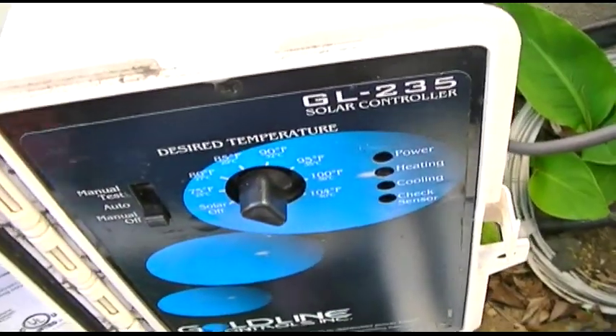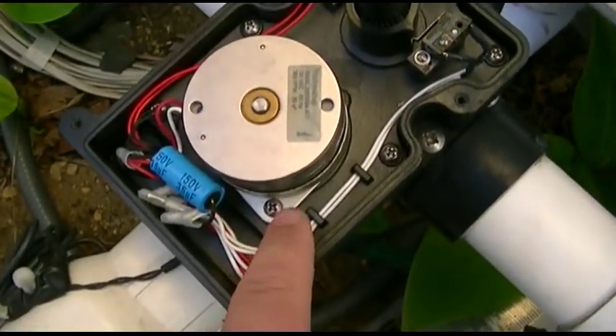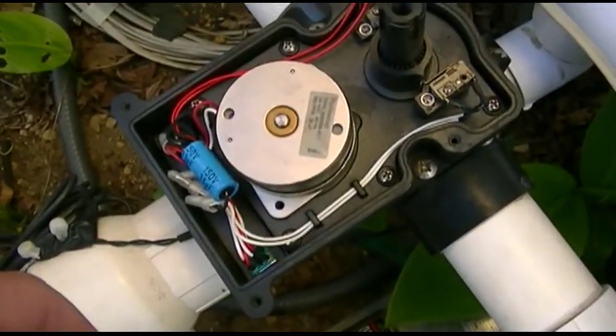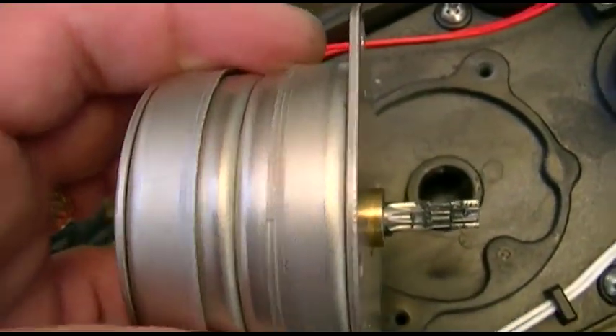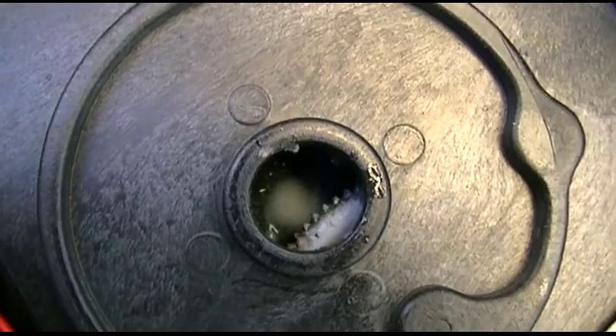The control box tells it to heat or cool, or open or close the valve. Anyway, let me show you what the problem is. You've got to undo these two screws to take the motor out. Now if you look carefully at it, it's worn. I don't know what a replacement looks like, but I would expect that the shaft on it would be all the same size. I took out the six little screws and looked at the gear train and everything in there looked fine. That looks all right although it may be worn - I cannot tell.